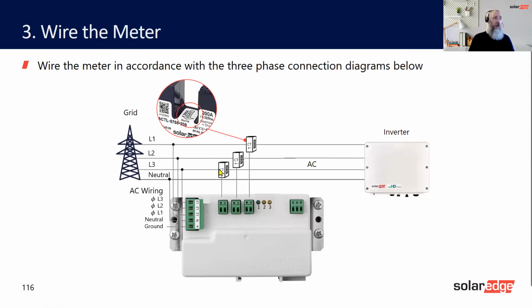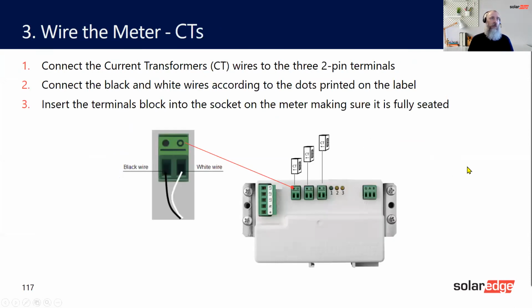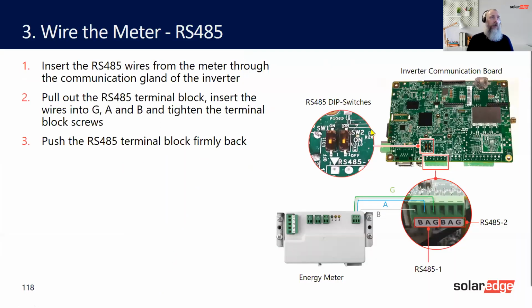So here are the CTs and the corresponding phases, L1, L2, L3, and you can see on here, and so on. And then you've also got your RS485 connections, A being the plus, B being the minus, and G being the ground. CTs themselves are connected as such. Remember, this is CT number 3, 2, and 1. Don't worry, you will get this presentation as well, so you don't have to worry about writing things down or screenshotting or such.